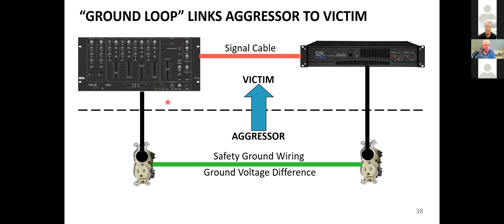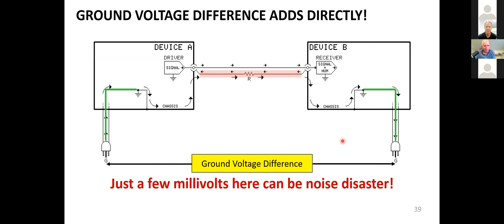But unfortunately, it also turns your system into an electrocution hazard. If something should go wrong, remember that 120 volts will travel through these signal cables. One piece of failed equipment with a lifted ground can cause the entire system to become electrified at 120 volts, or if this ground connection is really here and that one's interrupted, enough current will flow to burn the cable. Tens of amperes flowing through an RCA cable is not a good thing, and it's probably going to catch fire. So it goes from bad to worse. Unbalanced interfaces are just really not suitable for big systems.